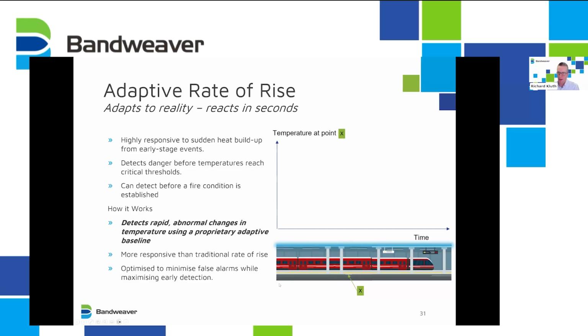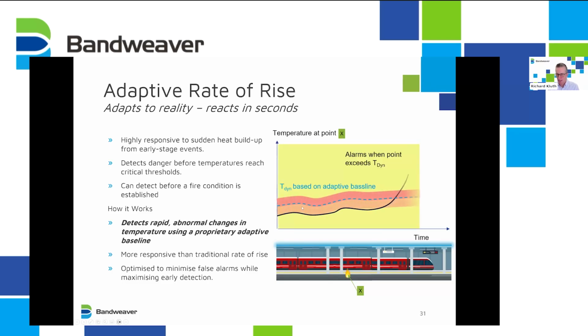So if we look at this graph here, we've got temperature on the y-axis, but this time it's time. So imagine we're looking at the temperature at this point here and how this develops over time. As you have a small fire developing, it starts to increase. You've got changes in the environment that the adaptive baseline follows, but when the fire develops and crosses that, that's when the rate of rise will change. And this can typically be set at 10 degrees C. So 10 degrees C is a lot quicker than waiting for 30 degrees C above the ambient threshold.